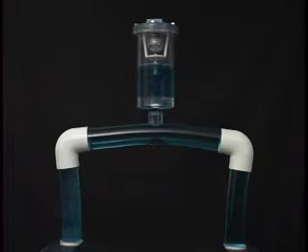Air vacuum valves, sometimes referred to as large orifice valves, are used to exhaust large quantities of air upon system startup, as well as allowing air to re-enter the line upon system shutdown or system failure. As water enters the valve, the float will rise, closing the discharge port. The valve will remain closed until system pressure drops to near zero psi. It will not open and release any accumulation of air while the system is under pressure.